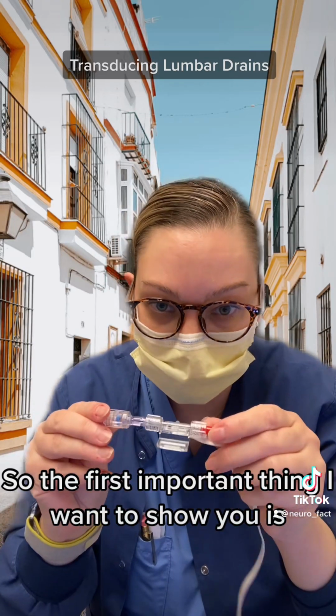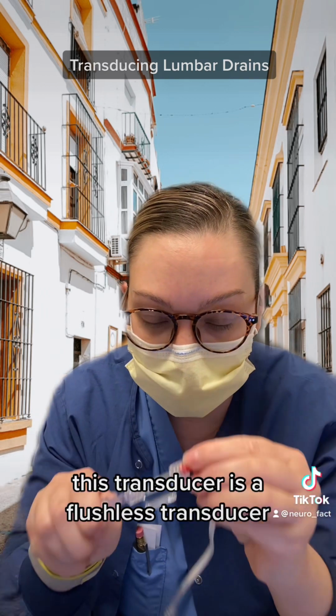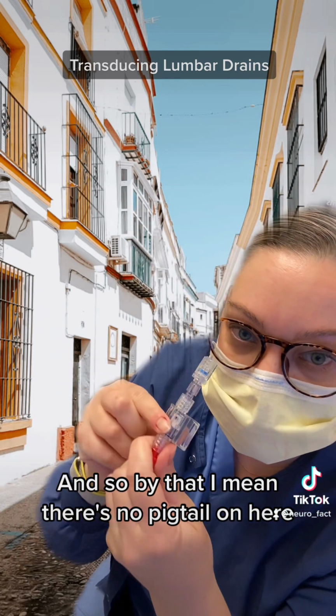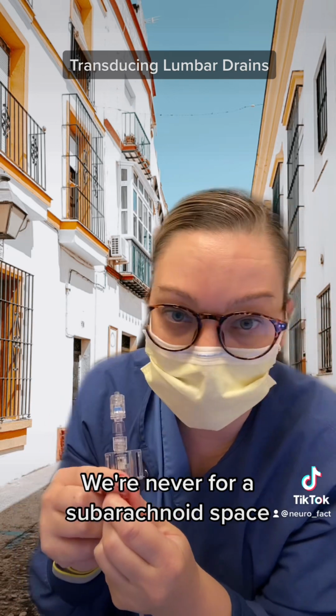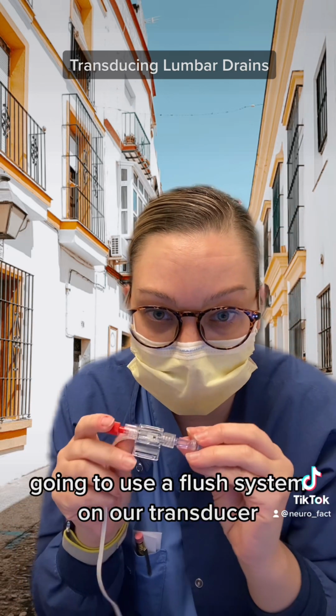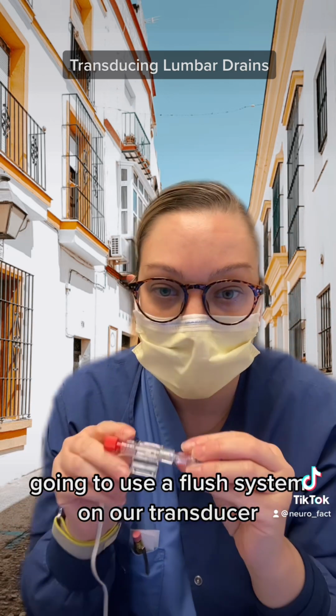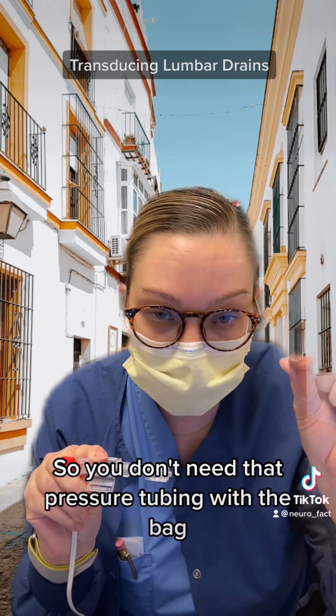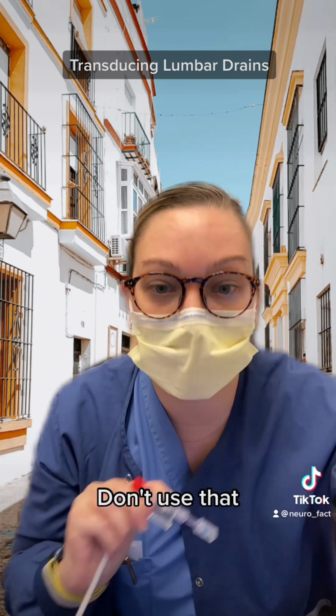So the first important thing I want to show you is this transducer is a flushless transducer, and by that I mean there's no pigtail on here. We're never for a subarachnoid space going to use a flush system on our transducer, so you don't need that pressure tubing with the bag. Please don't use that.